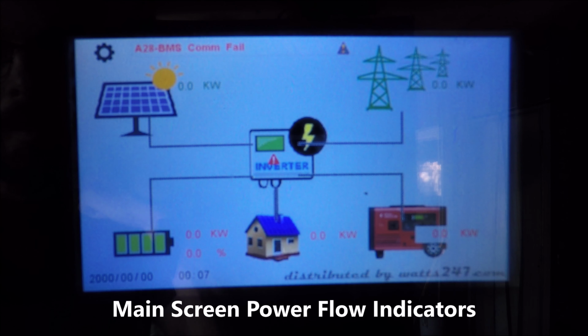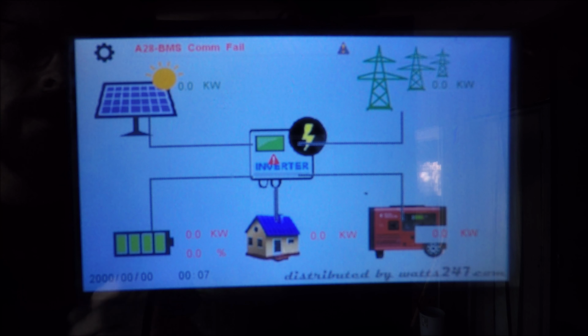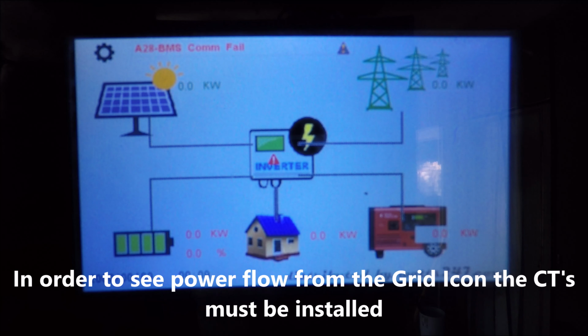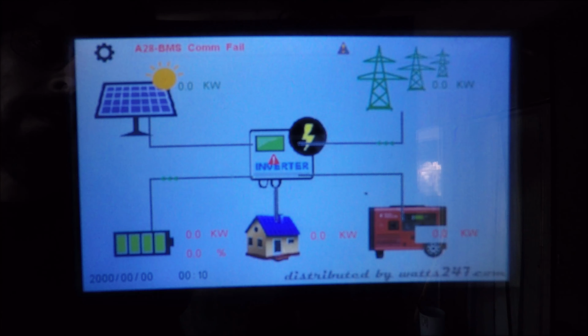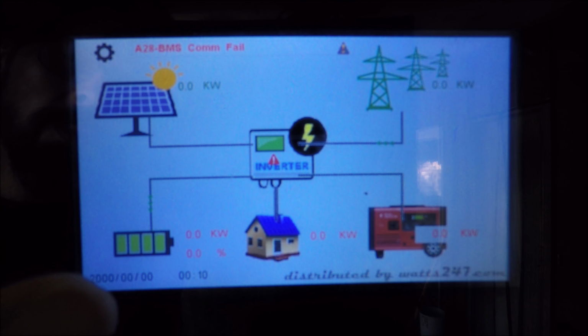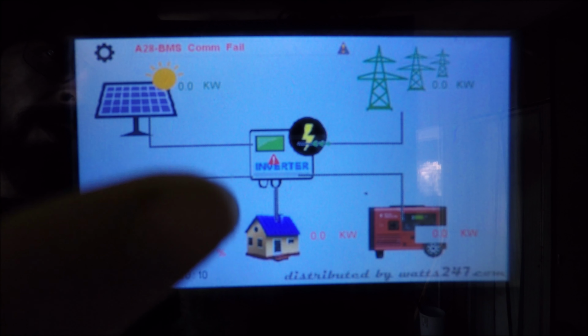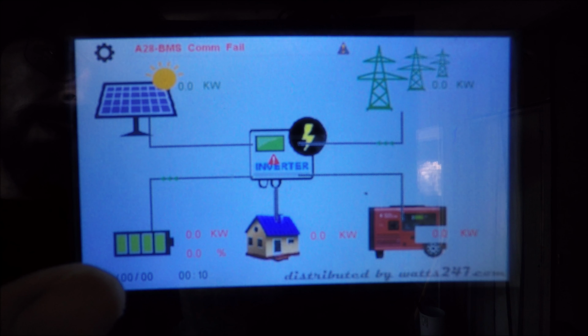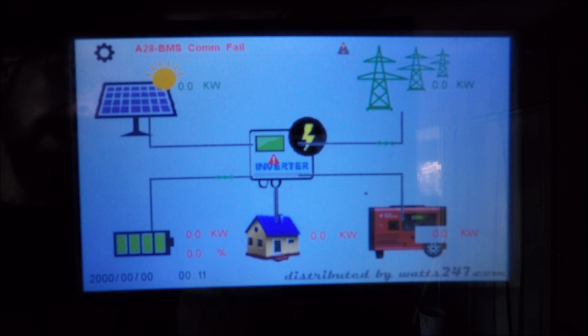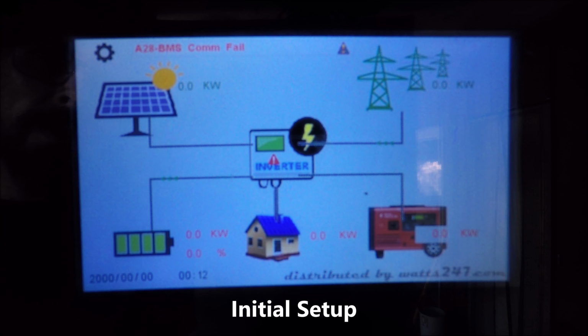As you turn on the different supplies going into the inverter, the battery, the grid, the solar, and the loads, arrows will begin to appear on these lines and show you the direction of the flow. As you can see, we now have grid connectivity, but because there's no load on the house right now, no power is coming in. But it does show that we have connectivity. We also have connectivity to the battery. We do have an error, BMS COM fail. This is because we do not have communication established between our battery and the inverter. We'll address this later. Now we're going to go through the initial setup process.